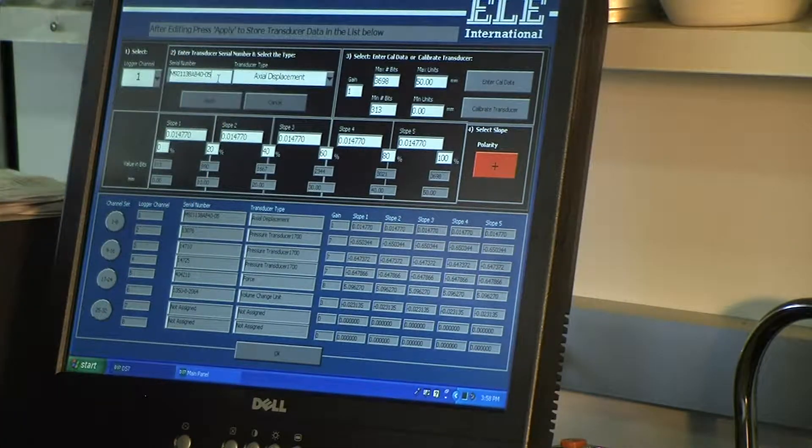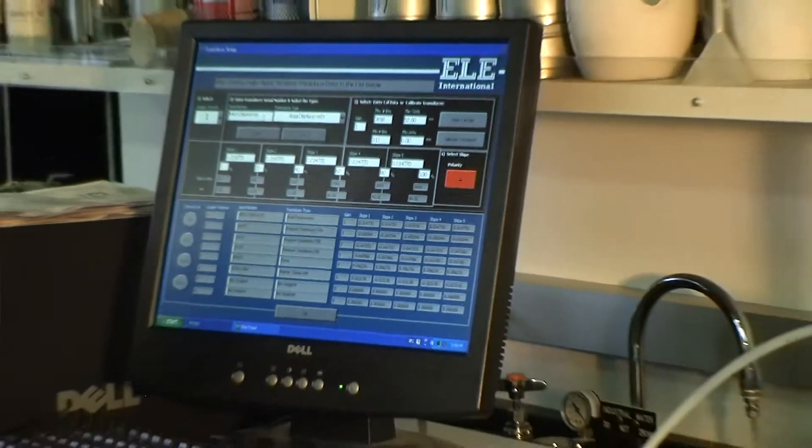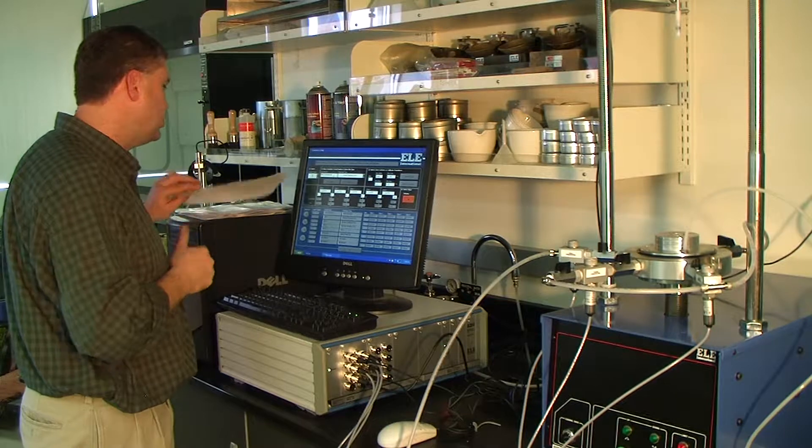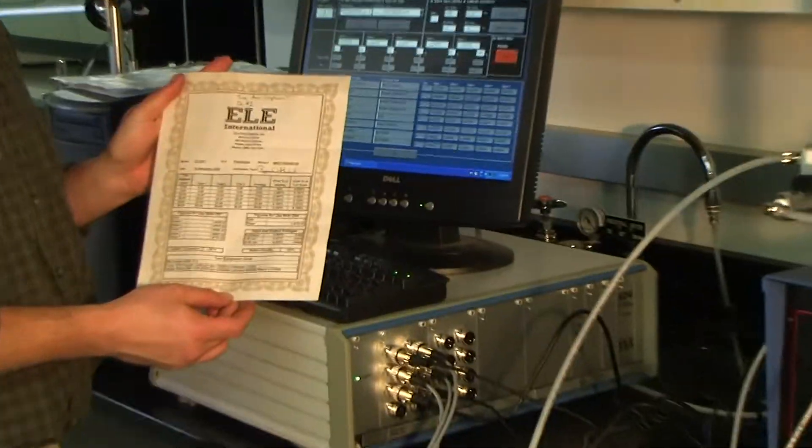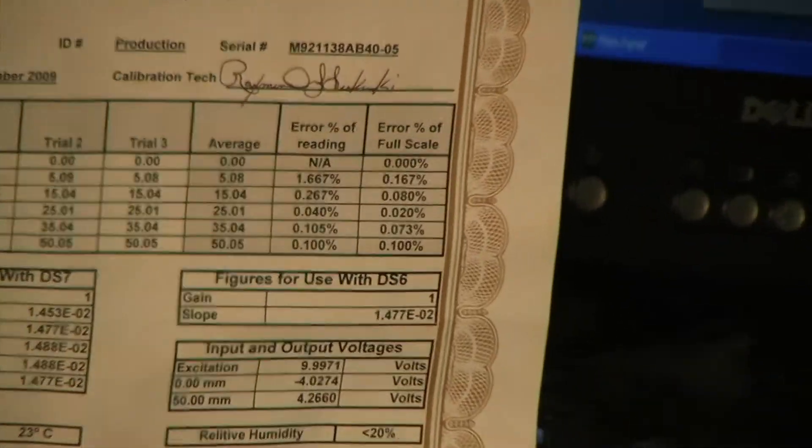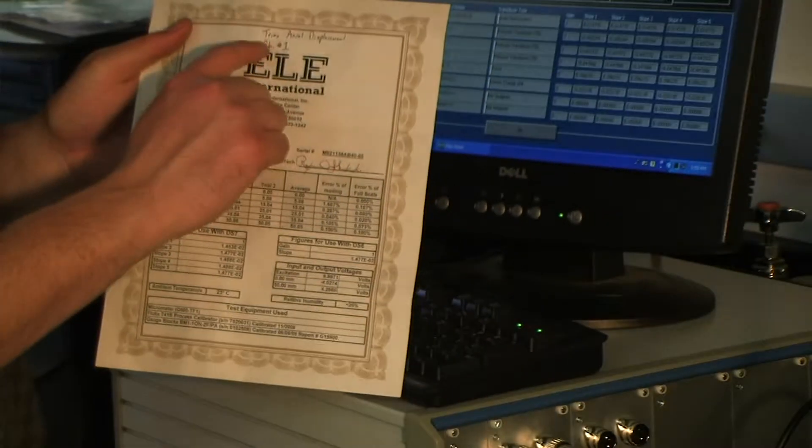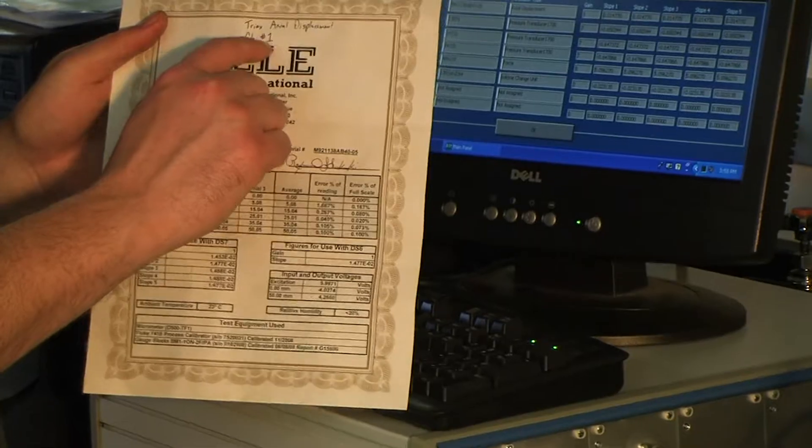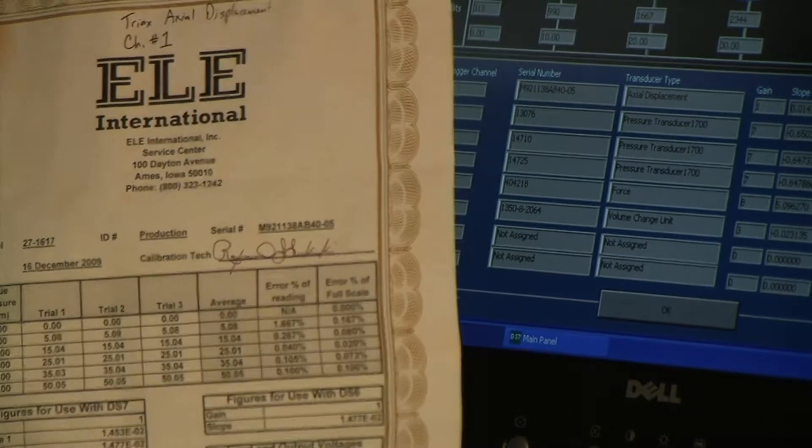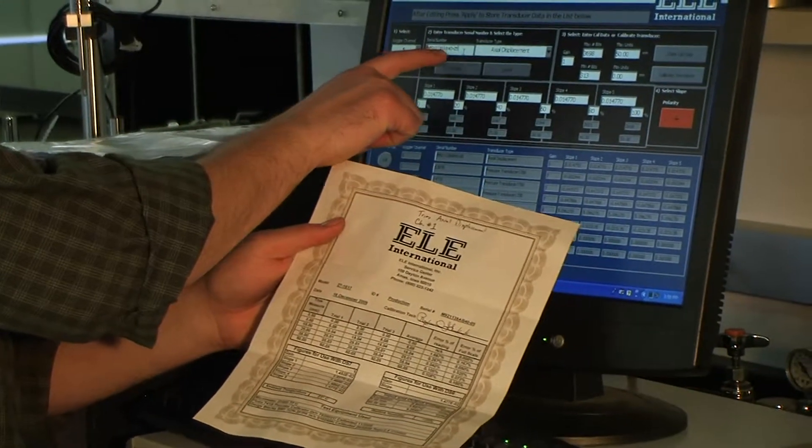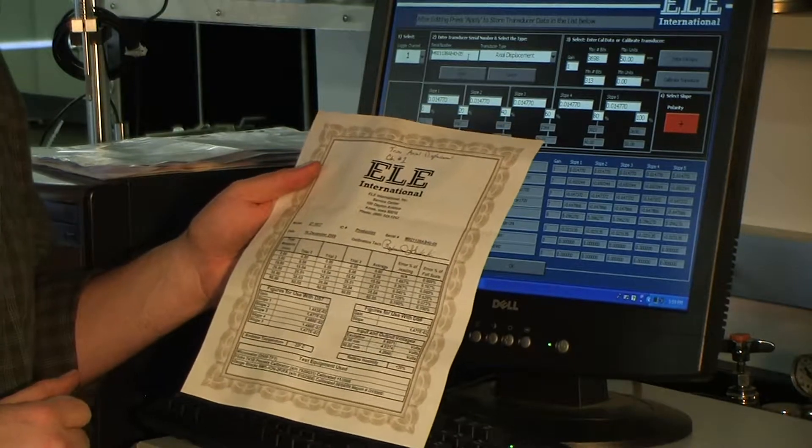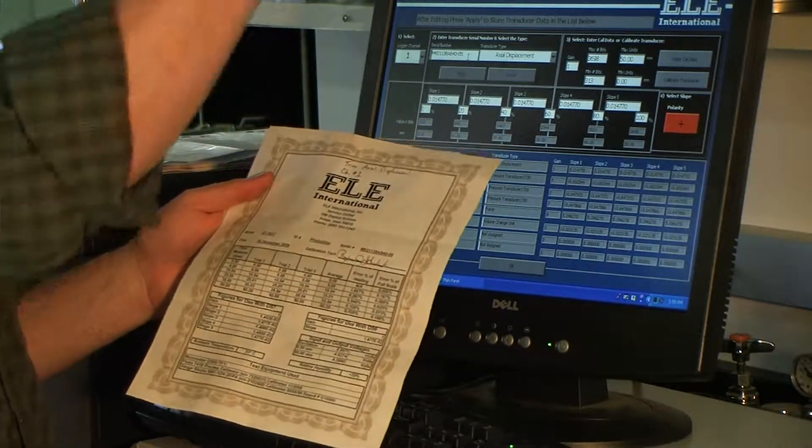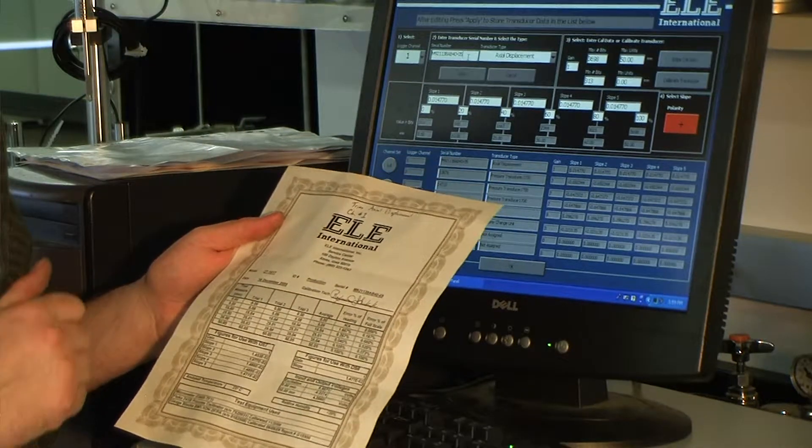This transducer is the axial strain transducer on the load frame itself. So I have, in the drop-down of the arrow, I have what channel logger we want to look at. We want channel 1. Here I entered the serial number off of the transducer itself. And I also verified that the transducer serial number matches what the serial number is on the calibration sheet that ELE sends out with the transducer itself. This is one version of the calibration sheets that are sent with each transducer. And if you notice, I wrote on the top, triaxial axial displacement channel number 1. So I've also written on here where that transducer should be plugged into for the ADU. And then I've verified the serial number on the screen with the serial number on this sheet and the serial number on the transducer device itself.